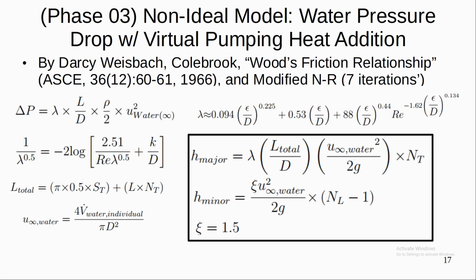For the water pumping losses through the pumps, I say pumping as virtual because in reality the chilled water is at a high pressure, and this whole thing can just be pressure fed, so to speak, but I still wanted to compensate for a pump just in case I was wrong about that assumption.